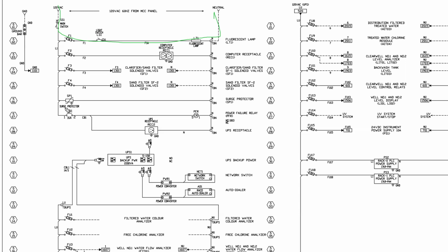This is a surge protector. It's labeled surge protector, so that helps. If you're not going to use standardized symbols on your drawings, hopefully you label what you have. Here we have, this says a 16 amp circuit breaker. So that's probably a typo, but maybe not. It's CB1. So here's an example of CB1 does not line up with CB57. So like I said, I worked for this company and this is how they labeled all of their equipment.